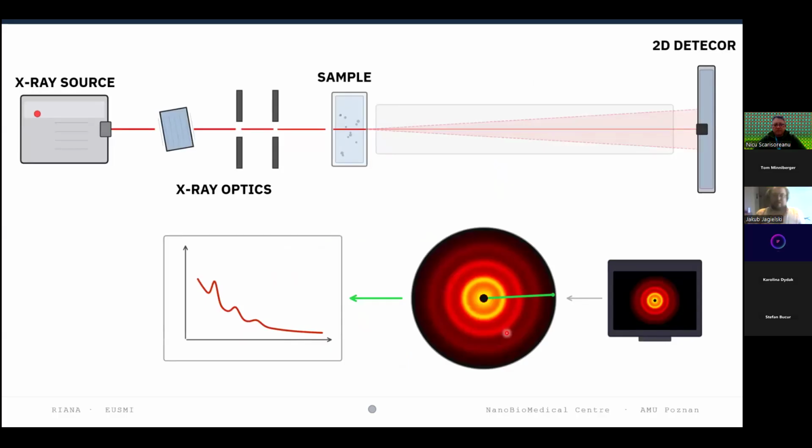Here's the SAXS setup. An X-ray source, either a lab source or a synchrotron, produces a beam that passes through a monochromator and collimation slits before hitting the sample in a capillary or thin cell. The transmitted beam is caught by a beam stop, while the scattered X-rays fan out at small angles and hit a two-dimensional area detector.